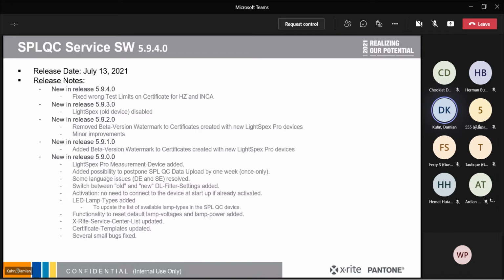SPLQC device with new daylight filters, or if you replaced the old filters with new ones during the last couple of months. Along with that, in the new service software, at the beginning of the calibration sequence, there is an additional prompt that asks whether you want to test with old or new daylight filter settings. The only difference between selecting old or new daylight filters is the illuminance upper and lower test limits for the daylight lamp source.